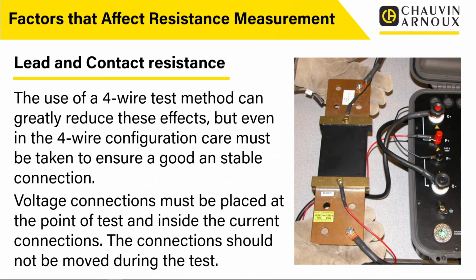Voltage connections must be placed at the point of test. We talked about this, so the voltage connection is where you're actually measuring, and these should be inside the current connections. The connection should not be moved during the test. So again, very important to think about lead resistance, think about contact resistance, but also nice clean surfaces, nice clean stable test connections. Less important when we get onto the 4-wire measurement, but for 2-wire measurement, it's vitally important.